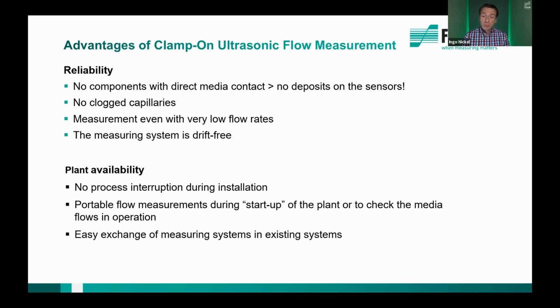And maximum plant availability is guaranteed because the installation can be performed without any process interruption. And during the startup, a portable flow meter can check the media flow. In operation, the media flow can be checked at different positions in the unit. And also a very important point, ultrasonic clamp-on flow meters are a retrofittable solution, which allows an easy exchange of measuring equipment in existing plants.